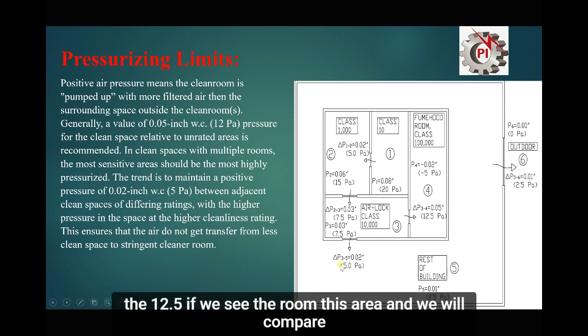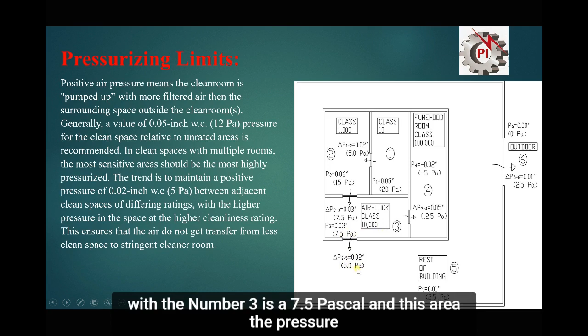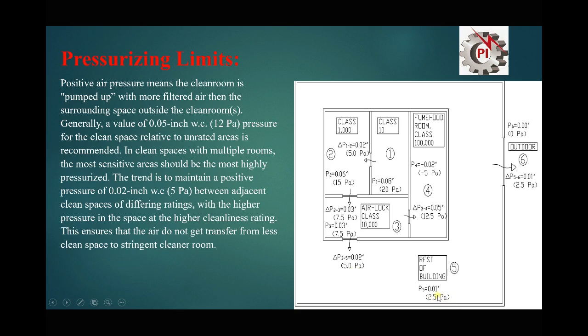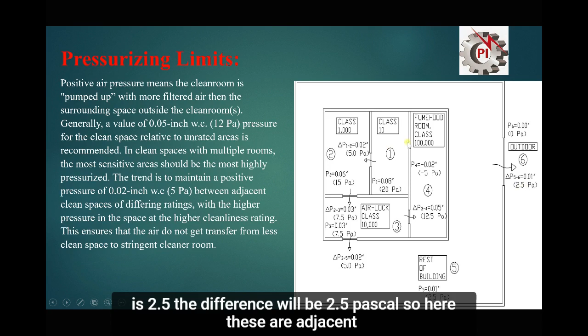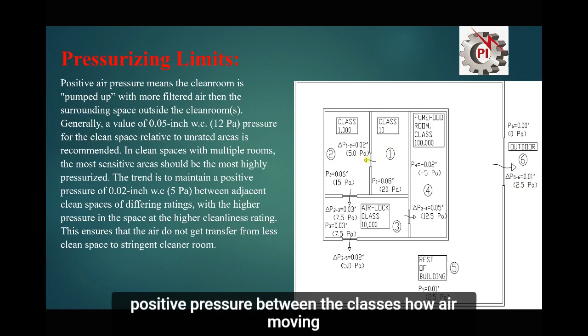If we see this area and compare it with room number 3, here it is 7.5 Pascal and in this area the pressure is 5 Pascal. The pressure here is 2.5 Pascal. This is the number 5 place. The difference between 7.5 and 2.5 will be 5 Pascal. If we see this place, here the pressure is 0 Pascal and here is 2.5, so the difference will be 2.5 Pascal. So these are the adjacent places, and we discussed how the positive pressure and the less positive pressure work between the classes, and how the air is moving from one room to the other room.